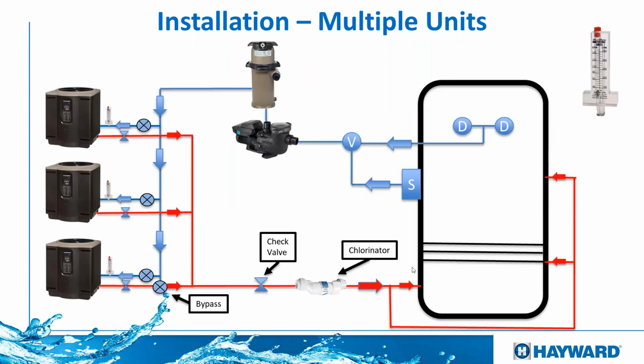Give me 1 second. Here we can see a different kind of diagram. Also same thing, chlorinator the last thing on the equipment line with a check valve before that. And then if we have several heaters, we want to make sure we install them in parallel. You can see here that we have a line coming in. We have a suction line here from 2 main drains and a skimmer into our pump, going through a filter. And then when it comes to several heaters, it splits equally. And then we have these little valves. As you can see here, the circle with an X mark. Those are valves. That way we can control the amount of flow that goes inside of each heater. And then obviously we'll have a flow meter so we can see how much flow is going through them.